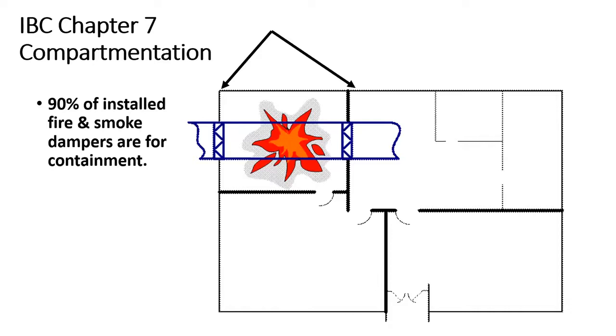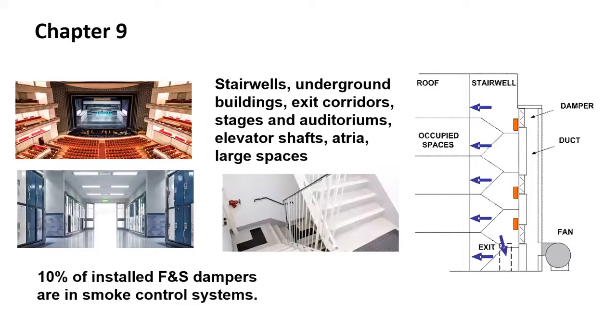So Chapter 7 is compartmentation. They're containment dampers, and their purpose is to stop fire or smoke from jumping out of the compartment of origin into other areas of the building. Next. Chapter 9 are much more complicated. We're going to see them in all the applications that are listed there. There are about 10% of those installed, and their main purpose is either to pressurize a space so that smoke can't flow into it, or to exhaust smoke so that it leaves the building. Stairwells shown there on the right side are a very typical example in most buildings where we're going to keep the stairwell pressurized so that people can escape in a relatively smoke-free environment.